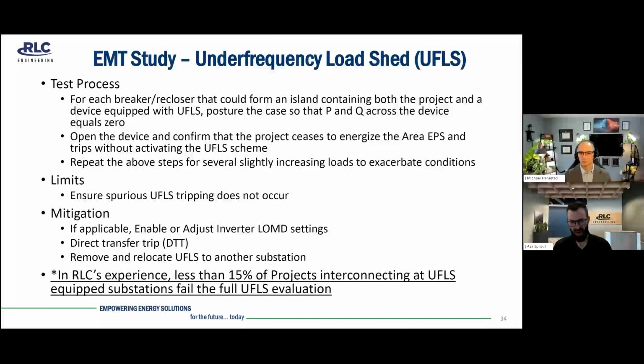Now, I will say, based on our research, we've seen some utilities utilize smarter technologies that'll actually look at the net flow through feeder devices. And if you have a forward flow, which would indicate load, then you could trip. But if it's a reverse flow, which would indicate more generation than load, then you wouldn't trip. But again, those are a bit more sophisticated, and I don't know if many people are using them yet. But another statistic here, 15% of projects at UFLS equipped substations fail the full evaluation. So that's an 85% pass rate and still pretty good.